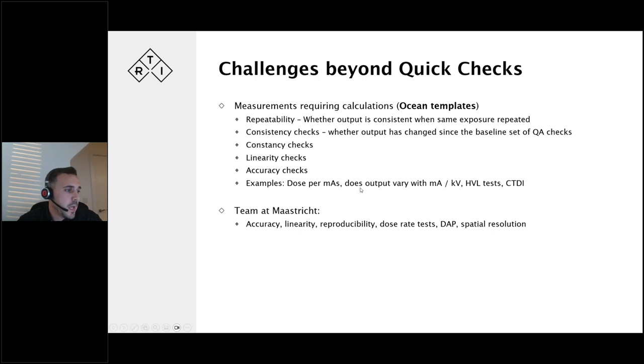Examples are dose per mAs - does the output vary with MA or KV? Certain HVL tests and calculating CT dose index. These are all measurements that require more than just showing display parameters.